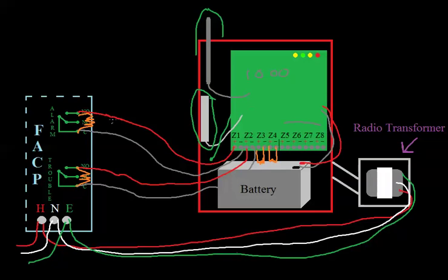So now it's just going to work the same way. I should use a different color here because I use that color on my battery. But the point is this is a complete circuit. So if the panel were to go into alarm, this would short out, just like we talked about before. Let's say it goes into alarm. Normally open. Open now closes, which is shorting out this radio, like we talked about before with current flow. Current's going to take the path of least resistance. So this is a little sloppy, but it's going to go through negative. And this continuity here through the alarm relay is less resistant, I guess, than the resistor. So the current's going to go up and you're going to get an alarm on zone one.